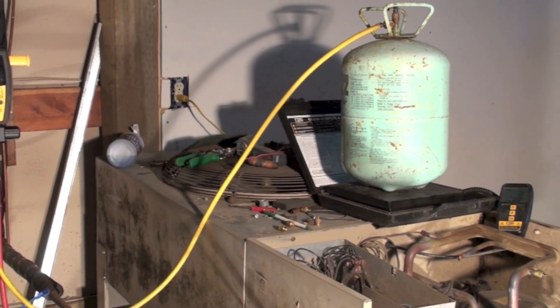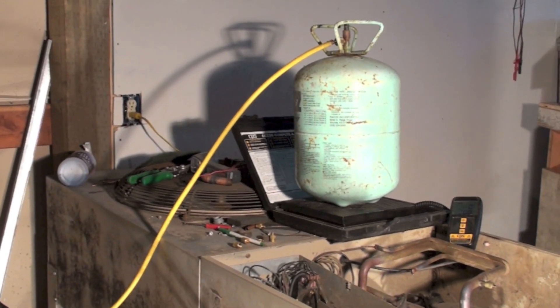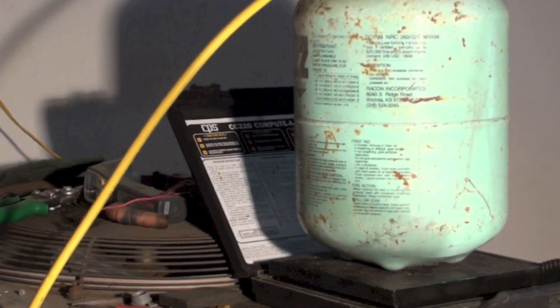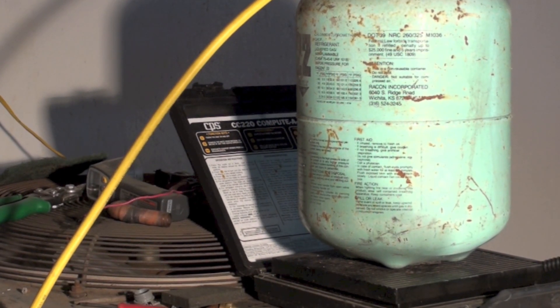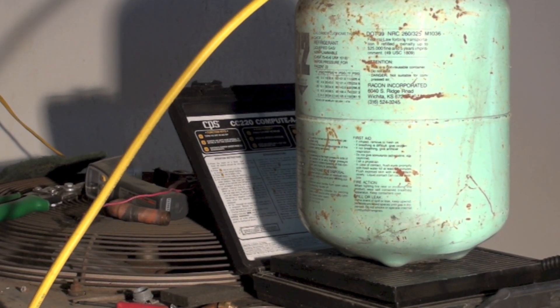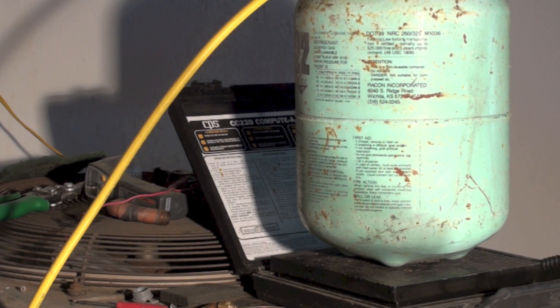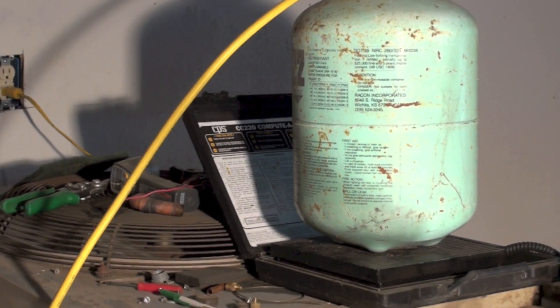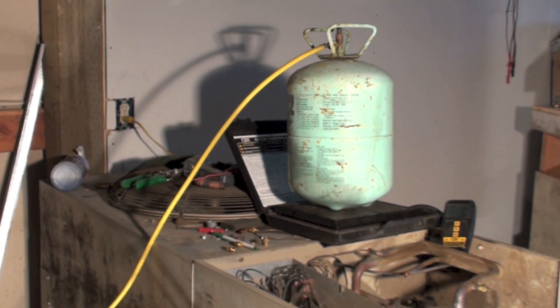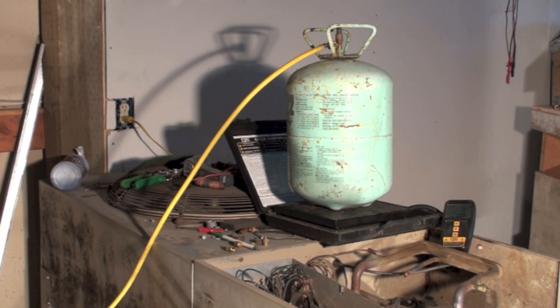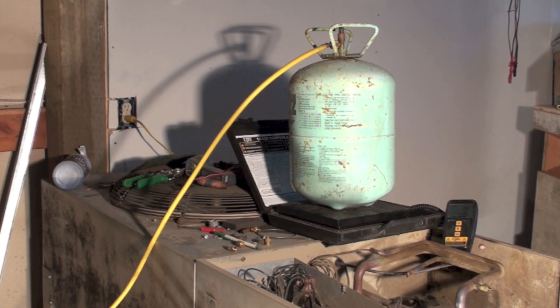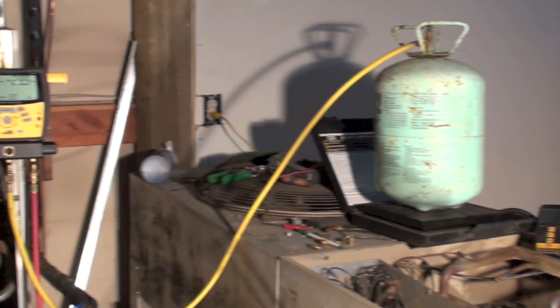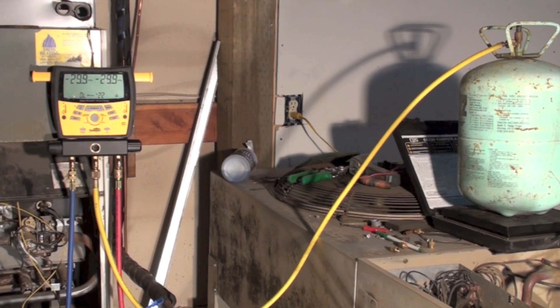Okay, if you look here, I've got the refrigerant cylinder right there. It's on a scale. I always have it on a scale. This is how I always do it. It just saves me trouble if there's questions later. It's on the scale, set to move gas out because it's upright, and you can see the yellow line goes over to the gauge set.